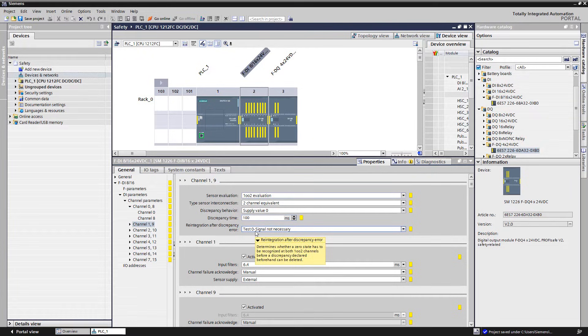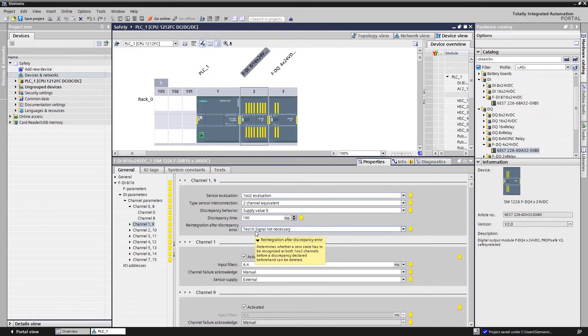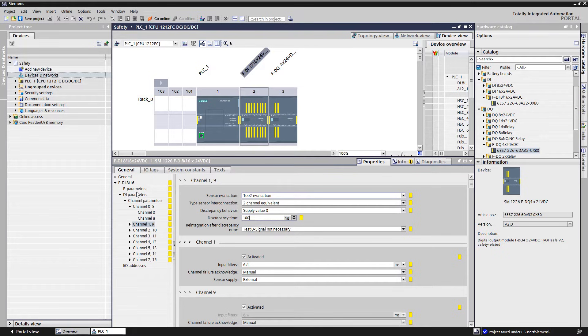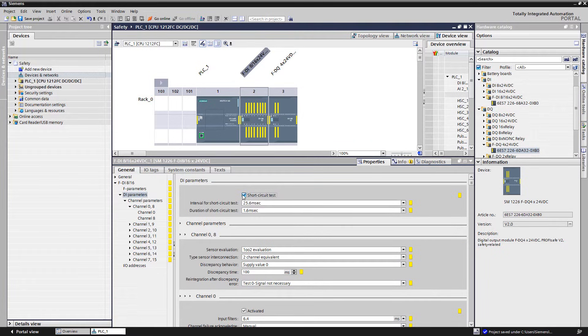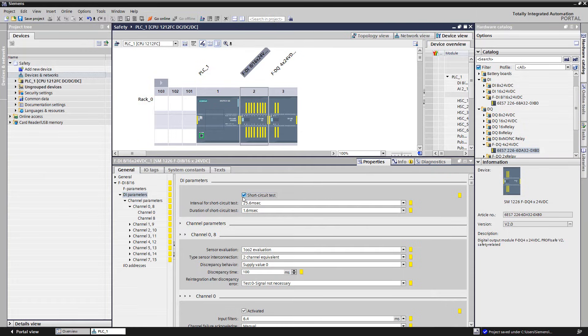All other setting parameters for the channel acknowledgement or input filter do not have to be changed. The default value is appropriate for most applications. For the diagnosis short circuit protection, the checkmark short circuit must be set for all 16 channels.